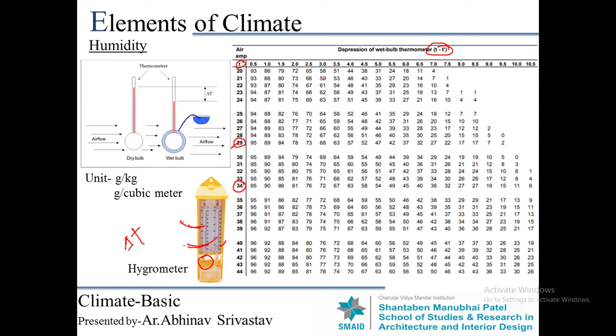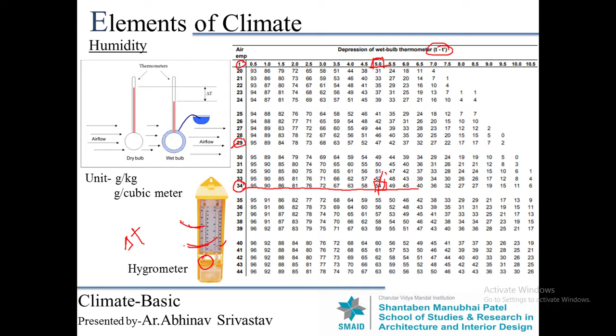Like, as an example, we take a 34 degree centigrade temperature measured in the dry bulb. Obviously the wet bulb temperature is lower than the dry bulb, so we just assume it is 29 degrees. So the difference is 34 minus 29, which is 5 degrees. So where is the 5? This one is the 5. So we consider this column and this row, and when we draw the line, the value is 54%. So the 54% is our relative humidity. Okay, so go for next.